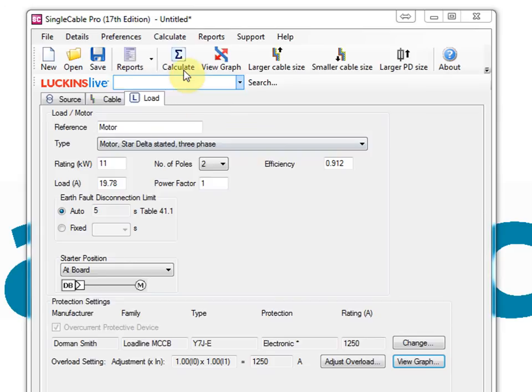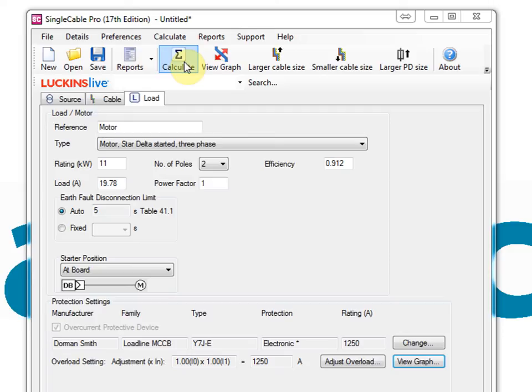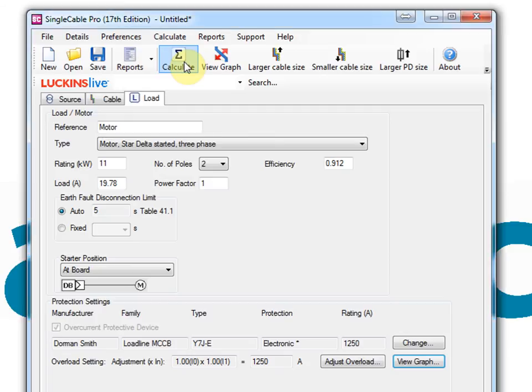When you click the calculate button, single cable quickly performs a wide range of calculations including protective device size rating, cable capacity requirements, line conductor adiabatic withstand, earth fault loop impedance check, earth fault disconnection check, and phase fault level.